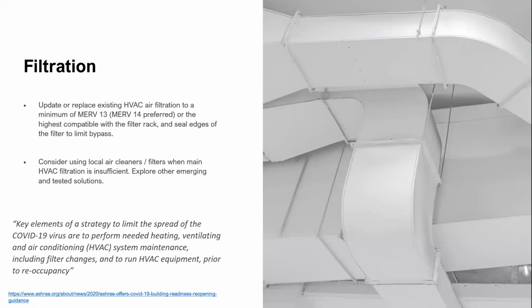The last slide is for filtration. Update or replace existing HVAC air filtration to a minimum of MERV 13, or MERV 14 if preferred, or the highest compatible with the filter rack, and seal the edges of the filter to limit bypass. If we could have MERV 13 for recirculated air as well as for fresh air, that would be best. A little better would be HEPA filters. HEPA is around MERV 16 to 17, which filters out 99% of the virus. MERV 13 can only filter out around 95% of the virus.